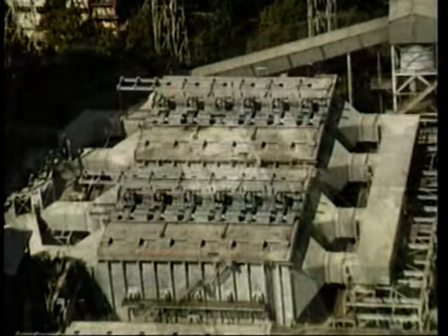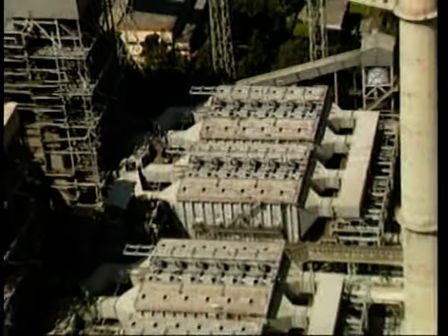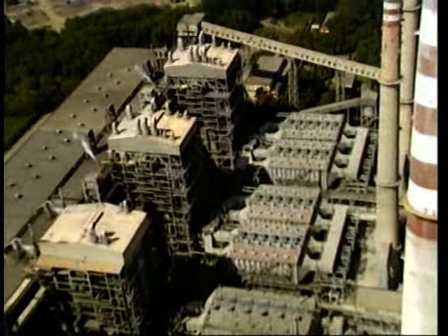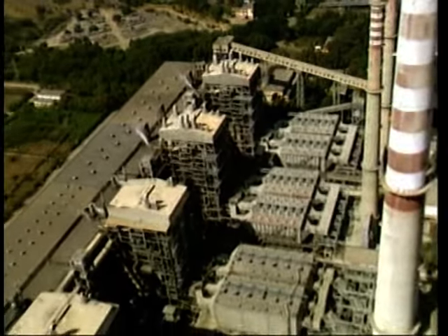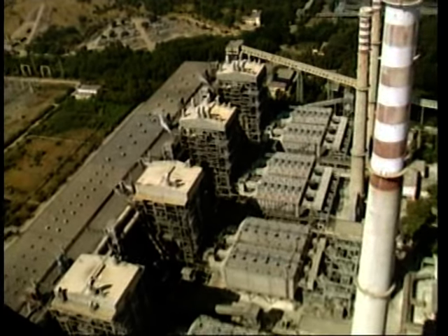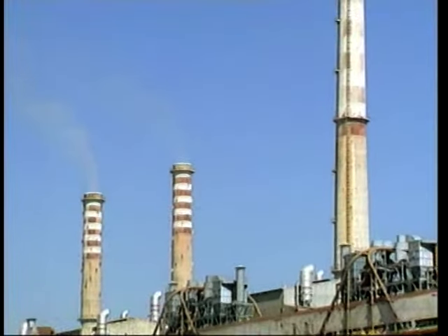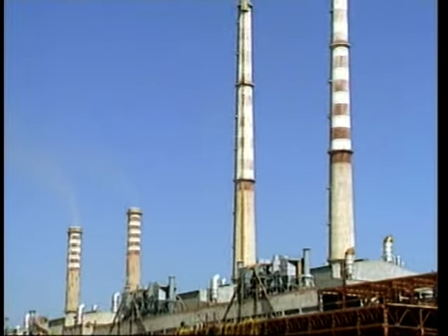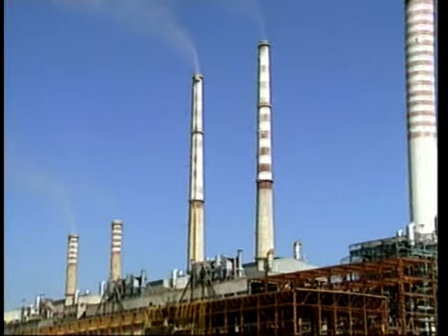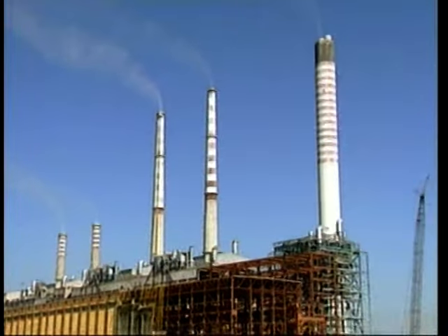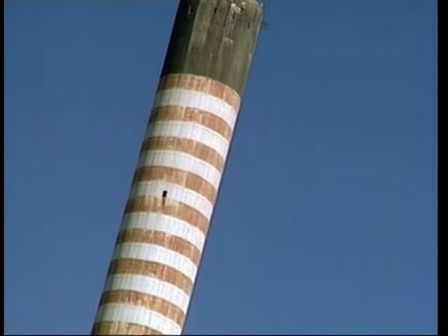To do this, each unit has an electrostatic precipitator. These electrostatic precipitators will suppress the ash and prevent the fumes released by the exhaust gases from being released into the atmosphere. This purified exhaust gas will be released in the air at 219 meters above the ground level through chimneys. There are totally 6 chimneys of varied heights. The chimney for units 1 and 2 is 119 meters, and for units 4, 5, 6 and 7 it is 219 meters. The fifth and sixth chimneys are built together in one mold.